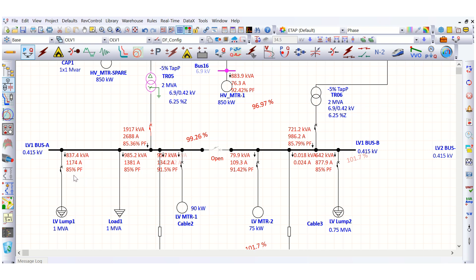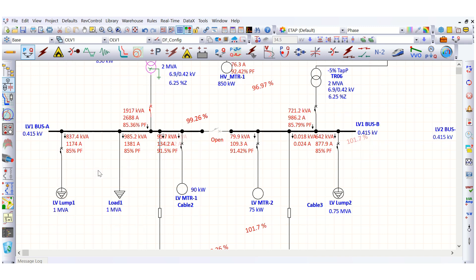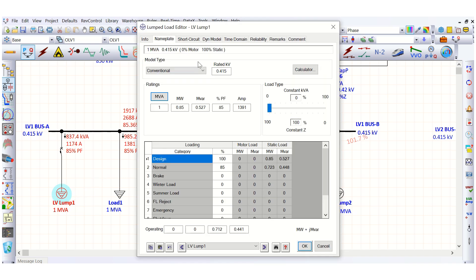Now you can see the power factor is 85% in both cases — matching. From these case studies, we should be very careful while modeling loads. Based on the load list of a particular project, we must carefully determine whether the loads being modeled are purely static loads or should be modeled as lump loads, because there is a basic difference — we will get different results. We cannot simply model a static load as a lump load or vice versa.